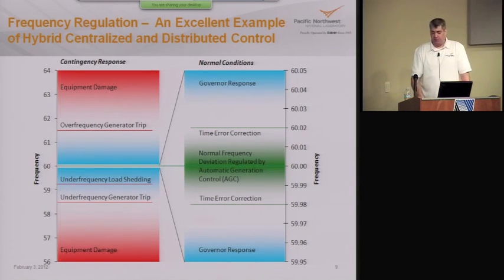There is still something called time error correction. NERC is actually debating whether to phase this out or not, but it's an artifact of the old days when the clock you had plugged in would keep time with the system frequency. If the grid ran at 59.99 hertz all day long, your clock would lose time. So what they do is measure the integral of that error and make up for it.